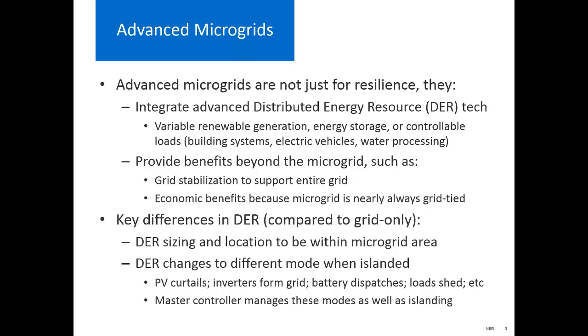The key difference in these distributed energy resources, compared to designing them for a grid-tie-only situation, is the sizing and location within the microgrid area. In that case, I'd run economic analysis to find my optimal size of PV, battery energy storage power rating, and battery energy storage capacity. But for a microgrid, I'll also look at the islanded situation and possibly choose a different size, and the DER will change to a different mode when islanded.